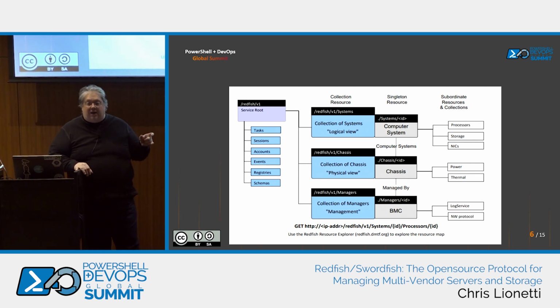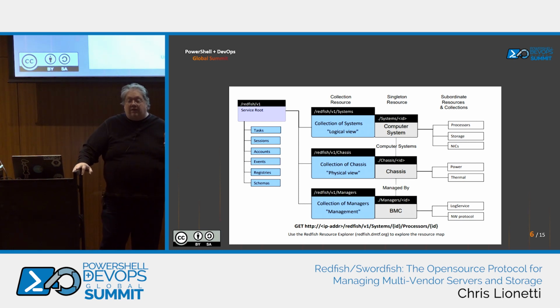But if you go down the session path, there's a session token action, which you can request, and you put in your credentials for your BMC, username, password, or whatever credentials you have set up on your BMC, and that could be Active Directory integrated, it depends on your BMC. You put that in, it'll send you back an authentication token. Once you have that authentication token, you can then run any commands you want. And it respects all the different levels of support.